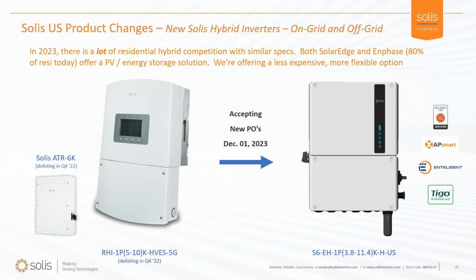The new product puts out 120/240 split phase natively. So you'll be connecting to your main breaker box with 240 split phase, and then connecting to your backup panel also with 240, 120 split phase. So you don't need the old transformer anymore - it's now natively 120/240 split phase, one less box to install. And you've got your integrated rapid shutdown device installed.